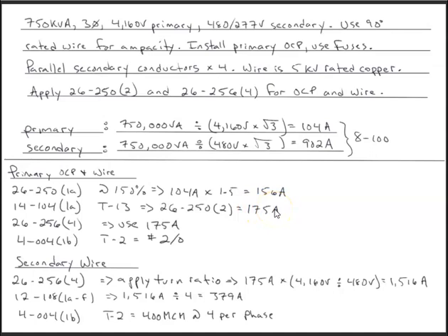We deal with the 175. So when we size our conductor, because we're using a 175 amp overcurrent device, we're going to size our conductor according to the overcurrent device. So because we've gone up, we will size our conductor accordingly, and then they will match. You want the wire and the overcurrent device to be as close as possible. And for the secondary wire, we're going to look at the current that we've chosen for our primary. We've sized the wire and overcurrent according to the 175, and we're just applying the turn ratio of the transformer for finding the secondary current. So we end up with 1,516 amps.